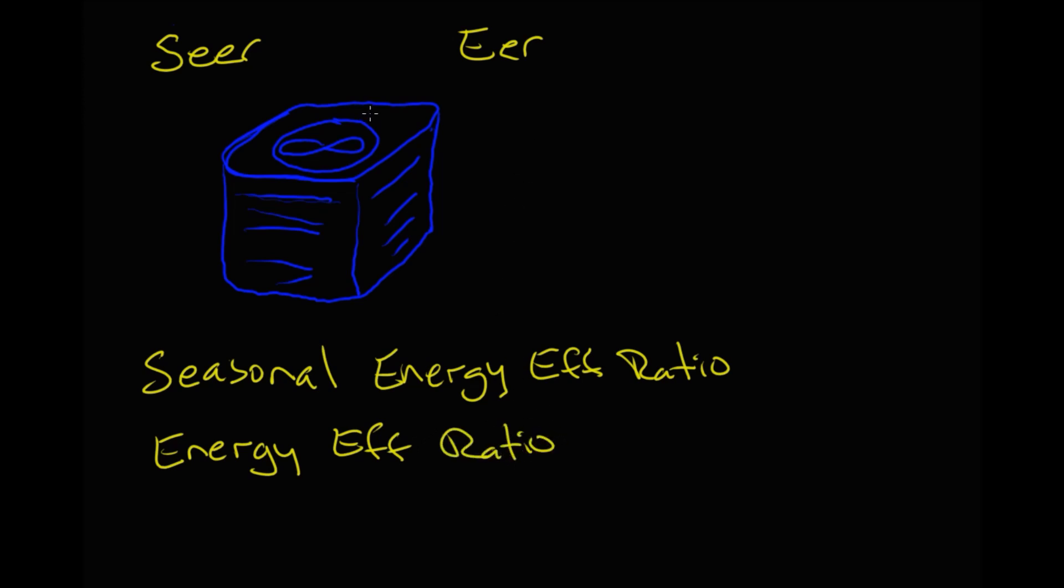What's the difference? Because air conditioners are rated by SEER and EER. And the rating organization that we use for this is called AHRI, the Air Conditioning Refrigeration Institute. They rate all equipment that's manufactured and sold in the U.S. They give it a rating, a SEER rating and an EER rating, and they also give it an AHRI number. That number tells us exactly what rating it has. We can look it up and see that the equipment's matched and that we're getting the actual rating. If it doesn't have an AHRI number, then it's not rated.